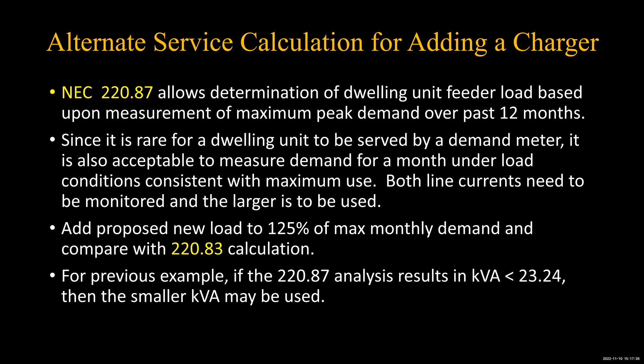If 220.83 works, then you don't mess with 220.87. But if 220.83 does not work, then you may want to try 220.87 before you go to the expense of changing your main distribution panel out, or your main service out. Okay. For the previous example, if your result came in less than 23.24 kilovolt amperes, then you can use a smaller one.